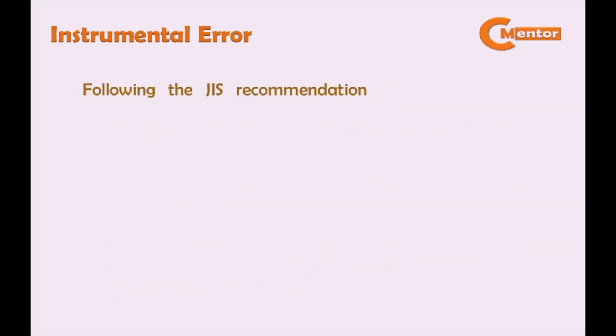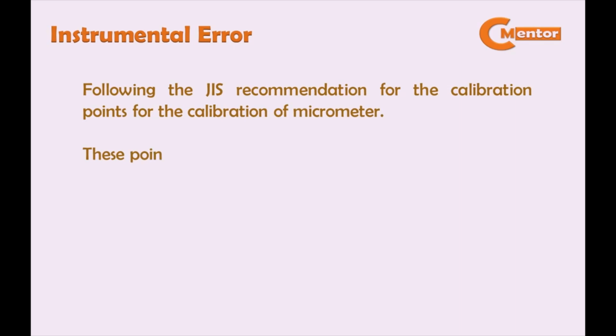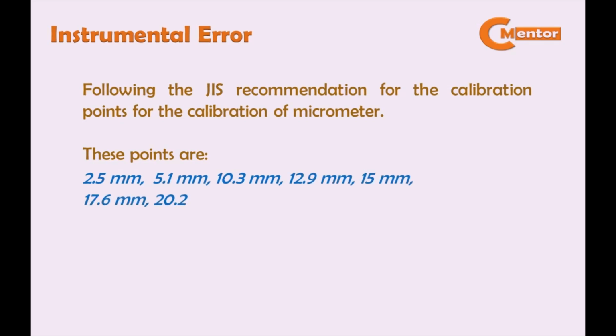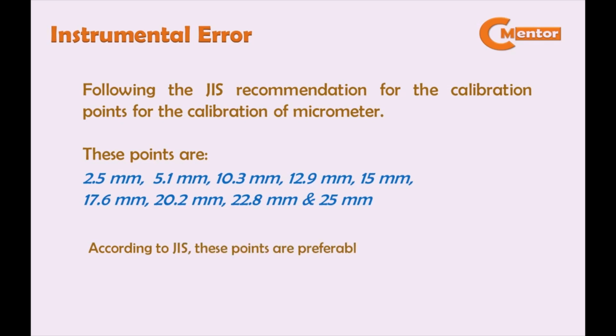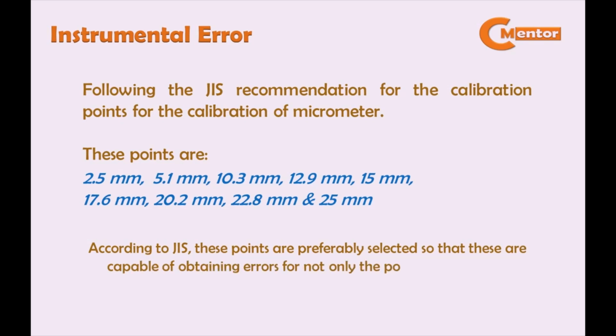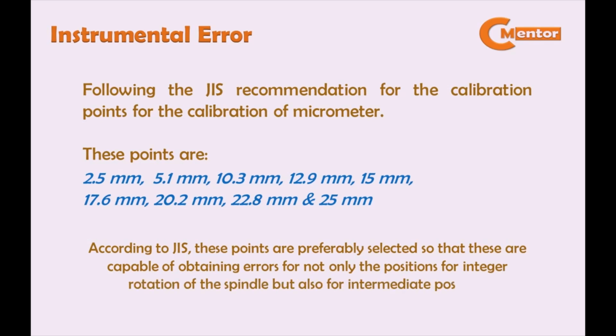Following the JIS recommendation for the calibration points for the calibration of micrometer. These points are 2.5 mm, 5.1 mm, 10.3 mm, 12.9 mm, 15 mm, 17.6 mm, 20.2 mm, 22.8 mm, and 25 mm. According to JIS, these points are preferably selected so that these are capable of obtaining errors for not only the position for integer rotation of the spindle but also for the intermediate position. Next is the actual video on how to determine the instrumental error of micrometer.